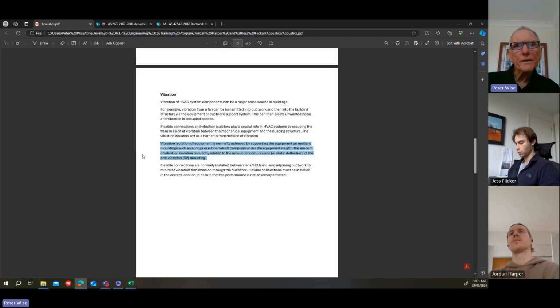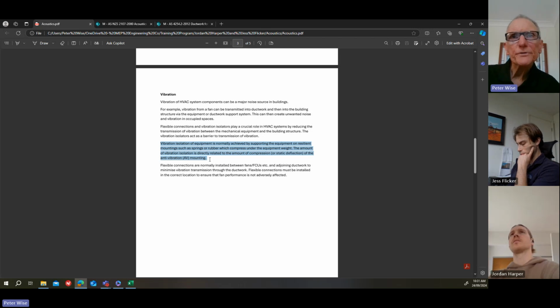When you're selecting a fan, smaller fans are usually mounted on rubber mounts, but the bigger ones would be on springs. The amount of vibration isolation is directly related to the amount of compression, or static deflection they call it, of the anti-vibration mounting.